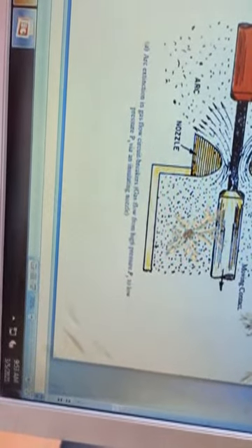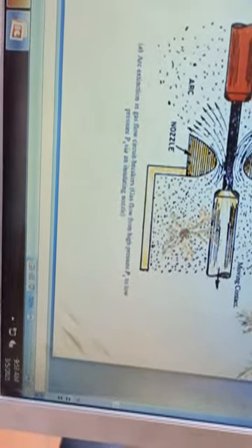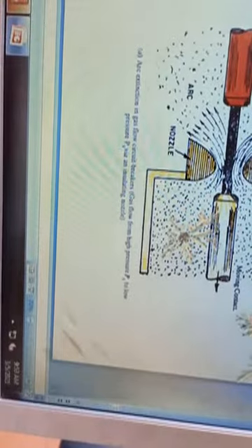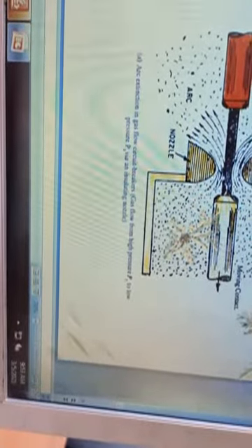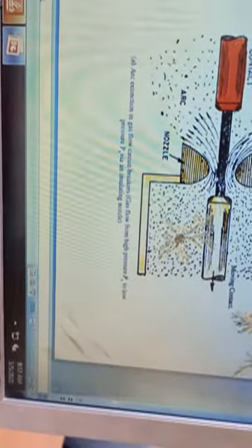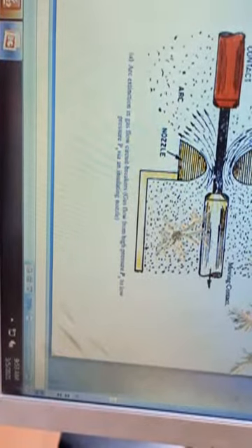Then some other properties. First is heat transferability. The heat transferability of SF6 gas is 2 to 2.5 times that of air at the same pressure. Then enthalpy, the heat content, at temperatures below 6000 K is much higher than nitrogen. And the next one is low arcing time constant.